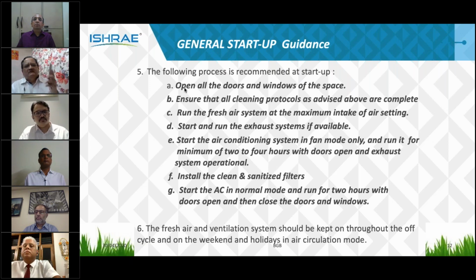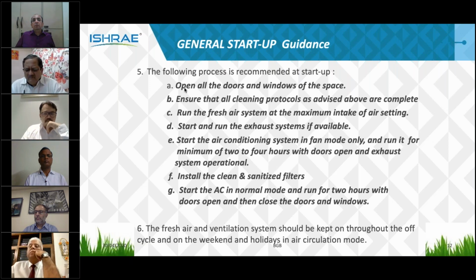Ensure that all cleaning protocols as advised have been completed. Run the fresh air system at the maximum intake of air setting, and then you start the exhaust system. It's not the reverse way. If you start the exhaust first, you'll find that nearby air is all getting sucked in. So fresh air is first, then the exhaust.